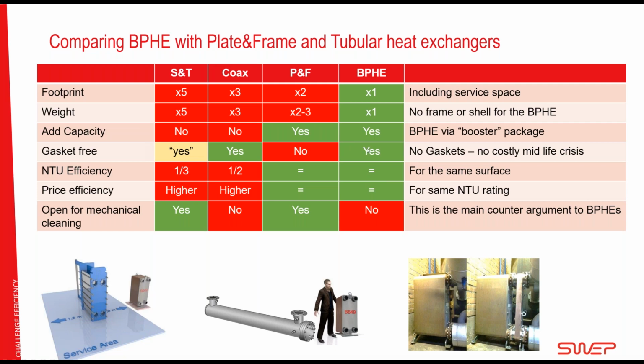So we have the coaxial and brazed plate that do not have gaskets. Shell and tube has a little bit, but they're not covering the whole product. And plate and frame are absolutely dependent on it. So I would say the most sensitive to gasket failure is the plate and frame. Efficiency as a heat exchanger, plate and frame and brazed plate are in the same area. The coaxial and shell and tube are worse, and this is considering the same active surface area. Price efficiency is a very common question. If we are looking at the same NTU rating, same heat exchanger efficiency, the plate and frame and brazed plate are clear winners compared to shell and tube and coaxial.